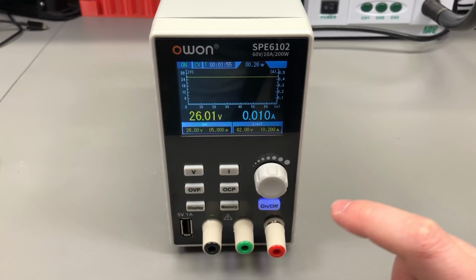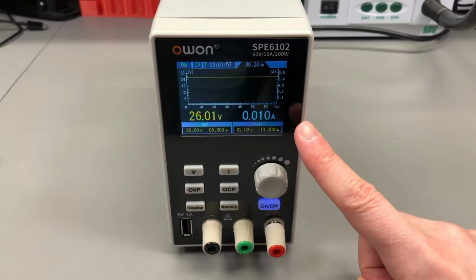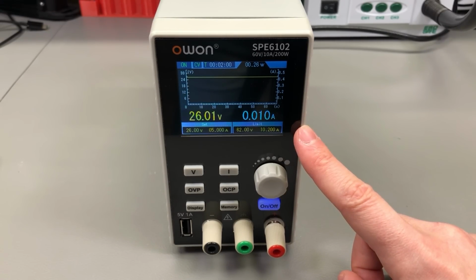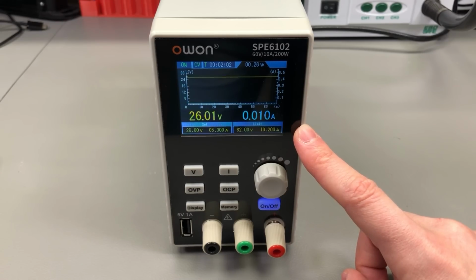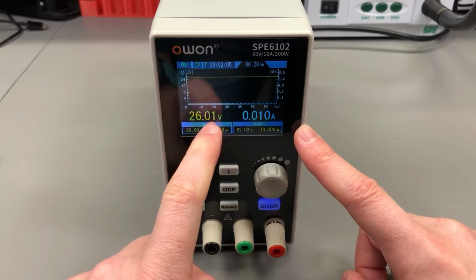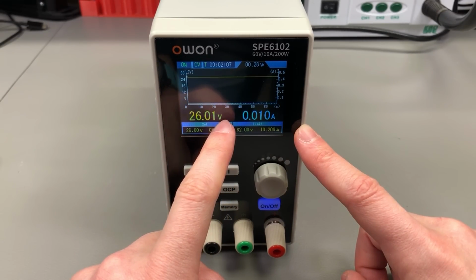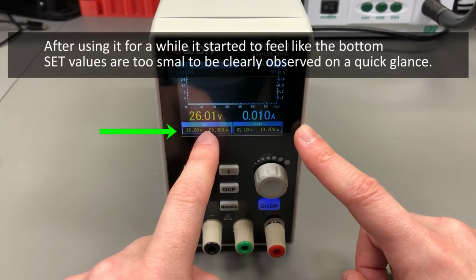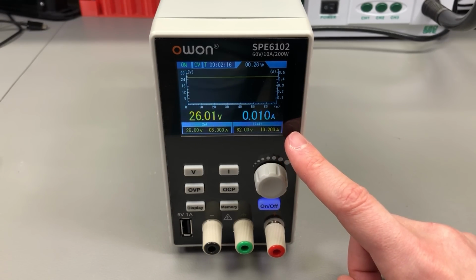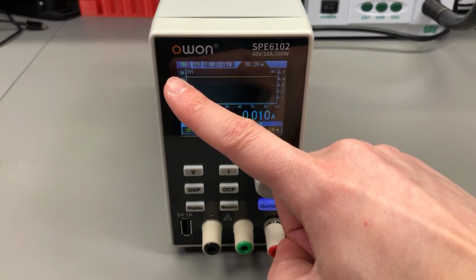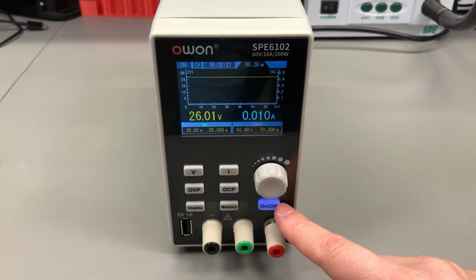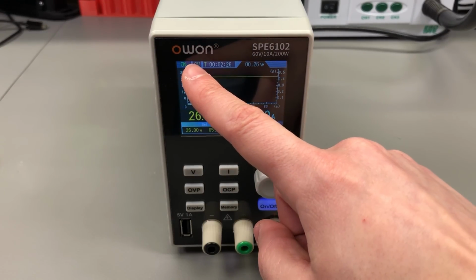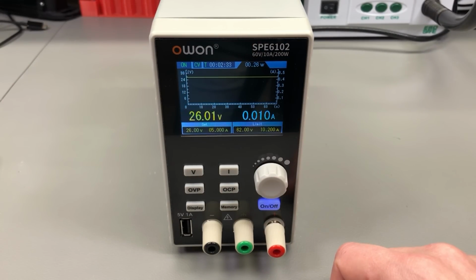It seems like the default screen mode is to show this graph of voltage and current over time, and we have the actual current and voltage values shown here, with the set values and limit values on the bottom row. That seems like a reasonable layout. On the top bar we have the on-off indicator, but that's better visualized through the switch indicator. We get the current mode, CC or CV, the time while the output is on, and a power indicator.